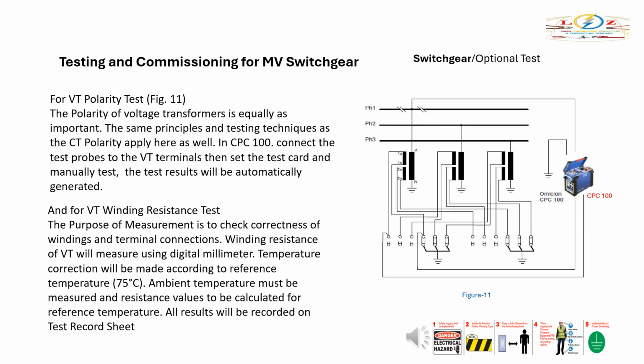For VT polarity test, as shown in Figure 11, the polarity of voltage transformers is equally as important. The same principles and testing techniques as the CT polarity apply here as well. In CPC 100, connect the test probes to the VT terminals, then set the test card and manually test. The test results will be automatically generated.